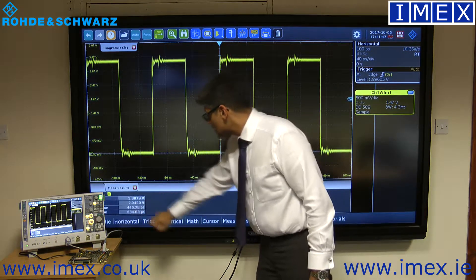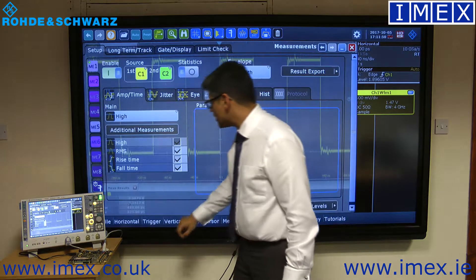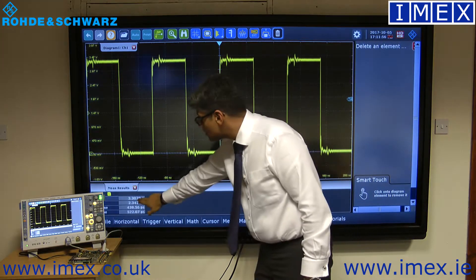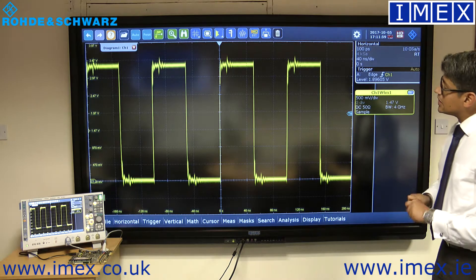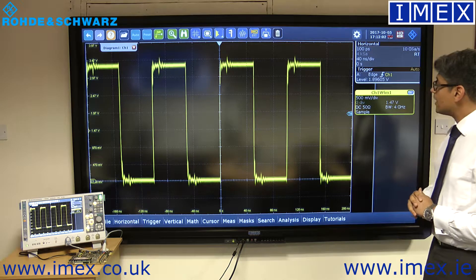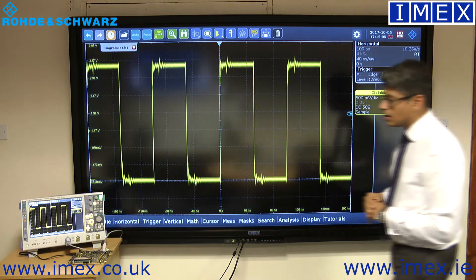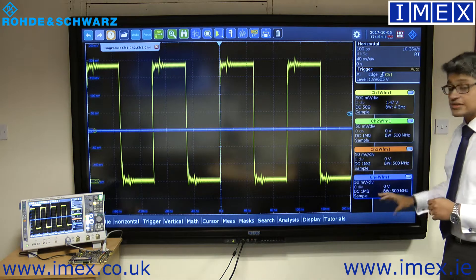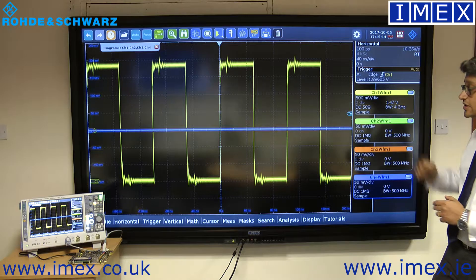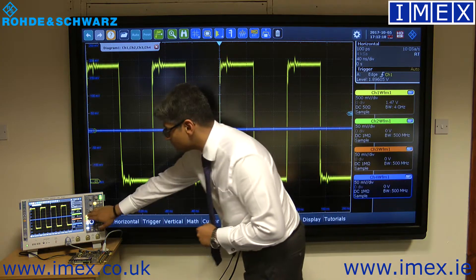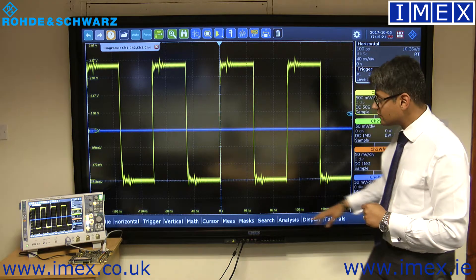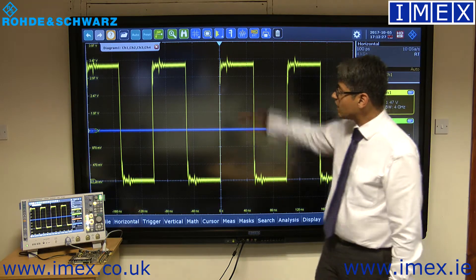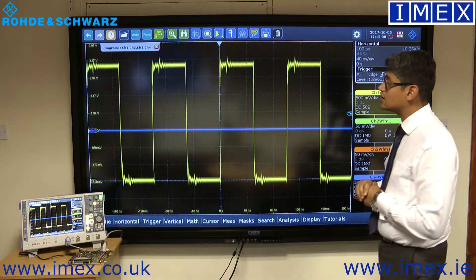You can tap the measurement result again to bring up the home menu for that particular measurement. Also, on the graphical area there are annotations for the channel currently in focus, so you can quickly see the time period and amplitude without needing to use cursors most of the time.